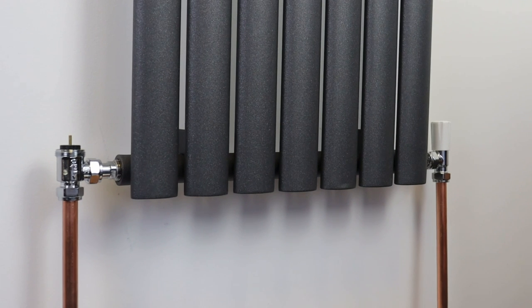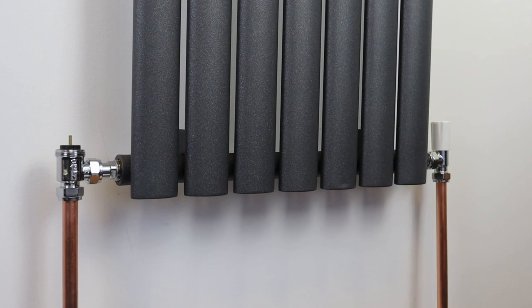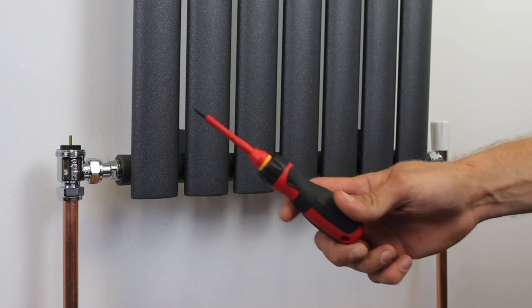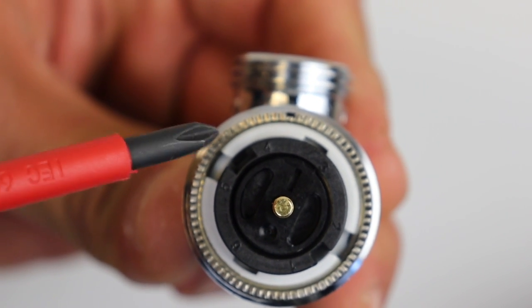When you're not using an auto-balancing TRV to balance a radiator system, there are two main ways of doing it: using the lock shield to restrict the flow into the radiator, or if you're using the Drayton TRV body that comes with the RT414 or the TRV4, you can set the balance on the TRV valve body itself.